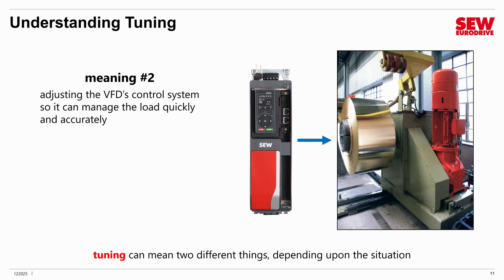Meaning number 2 means adjusting the VFD's control system so it can manage the load quickly and accurately. I'm showing you an application here on the right, which is an excellent illustration of why you have to tune the VFD. You may have seen one of these before. It is a sheet metal winder. It rolls up a gigantic sort of toilet paper roll of sheet metal. As you can guess, there's a lot of mass in that roll. That thing is incredibly heavy. And if you've ever taken a physics class, you know that mass is equivalent to another property of matter called inertia. Inertia is the property of matter that makes it resist changes in its motion. If you try to move something which is not moving and it's got a lot of mass, it's going to be very hard getting it moving. But once it's moving, if you want to stop it, it's very hard to stop it.